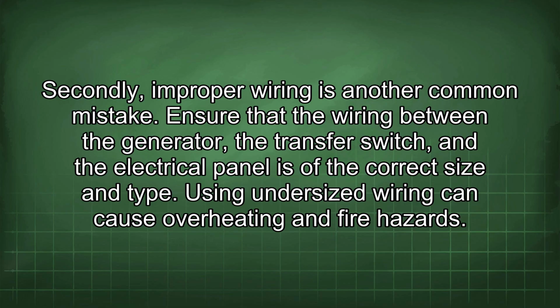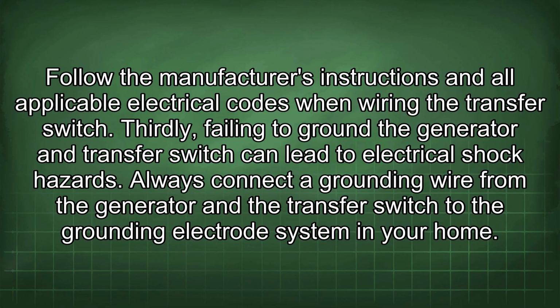Secondly, improper wiring is another common mistake. Ensure that the wiring between the generator, the transfer switch, and the electrical panel is of the correct size and type. Using undersized wiring can cause overheating and fire hazards. Follow the manufacturer's instructions and all applicable electrical codes when wiring the transfer switch.